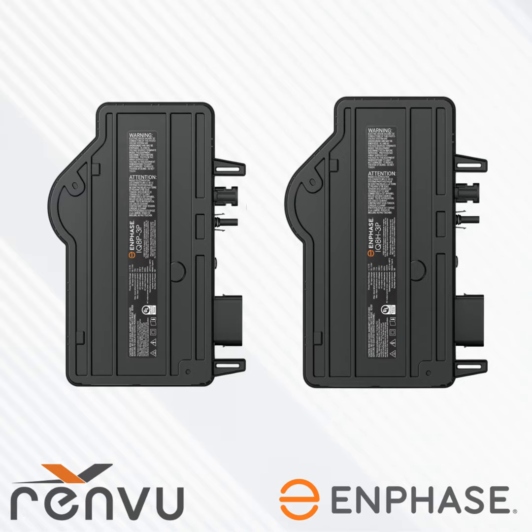Your clients love us for that too. That AC output is sent out to a parallel AC circuit via the Enphase QD cable. It lands on a sub panel, which has overcurrent protection devices, aka breakers. In the case of this system, those are 20 amp 3-pole, 3-phase breakers, and you build that yourself. That goes onto the utility panel, where it goes onto the grid or gets used by the loads of the building.